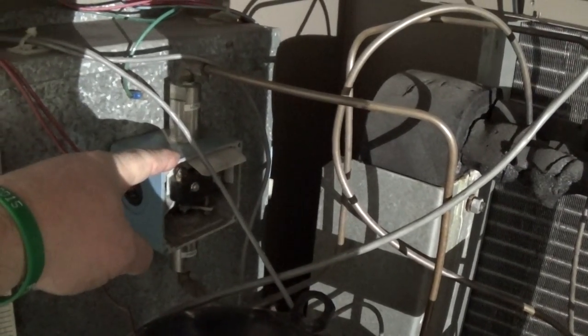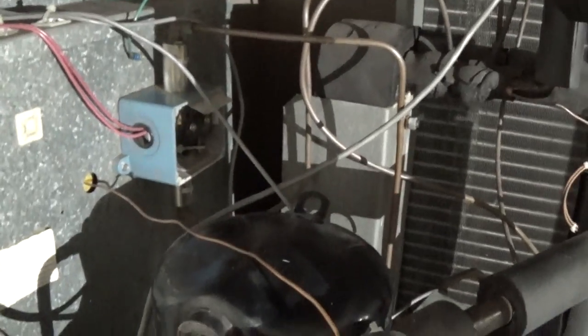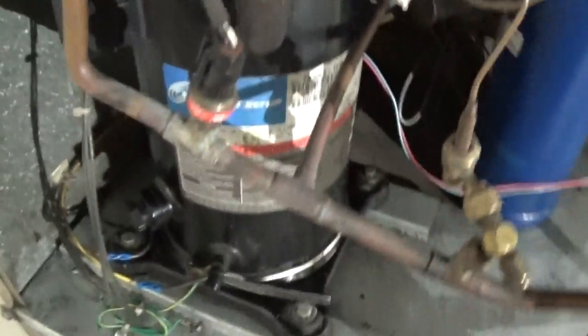Now, this has a nice flow switch which goes off pressure differential of the fluid flow, or the glycol flow. It senses the high side and the low side of the glycol flow, and if there's no flow at all, that will stop the chiller. We have transducers for the pressure. These are fixed ones, okay? And those tie back into our controller, which I showed you earlier.